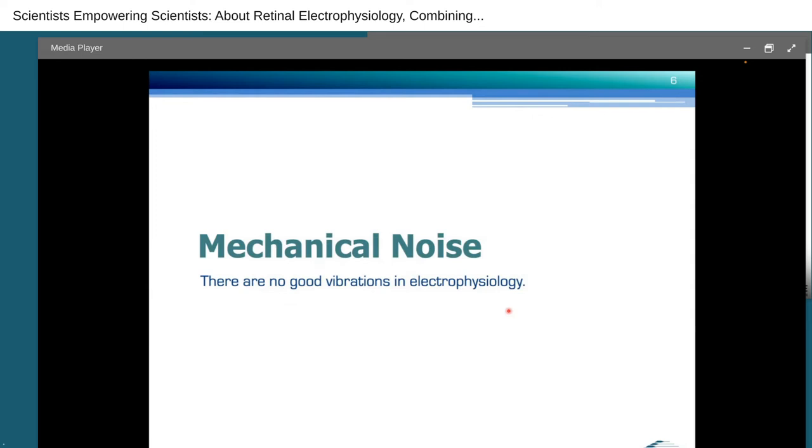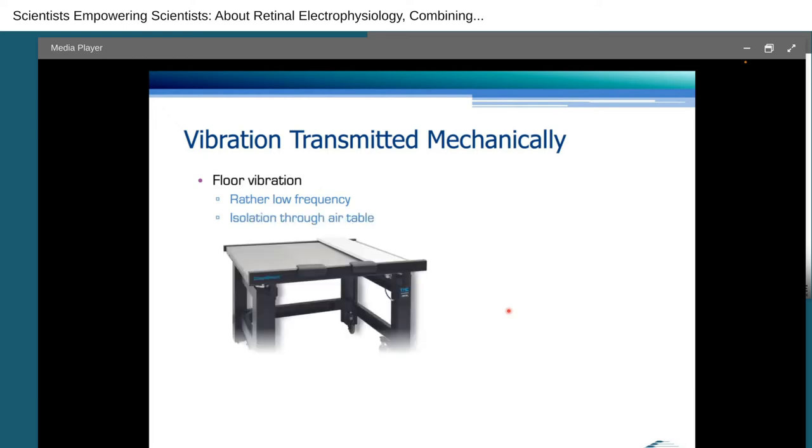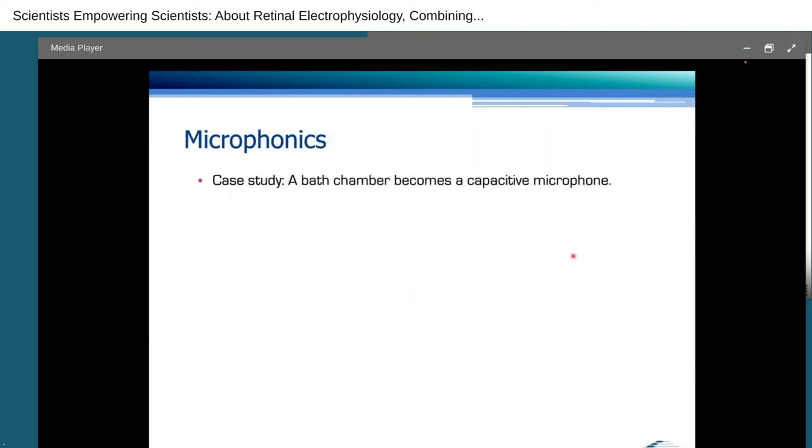Let's switch over to mechanical noise. There is no such thing as good vibes in electrophysiology. Vibration is usually transmitted mechanically, either via floor vibration, that happens at a rather low frequency, and can be pretty well isolated through using an air table, a tabletop that floats on air dampers, air cushions. Here's the isolation performance. Lower value means lower transmissibility, so better damping. The frequency range that we're looking at here is between 10 and 70 hertz, so relatively low frequency. You can also have mechanical vibration, mechanical noise by fans or other equipment that touches components. I once had a fan duct sitting on the lamp housing of a microscope that gave me a lot of grief, or microphonics, and also that gave me a lot of grief. And that's an anecdote, a case study that I want to elaborate a little further on.